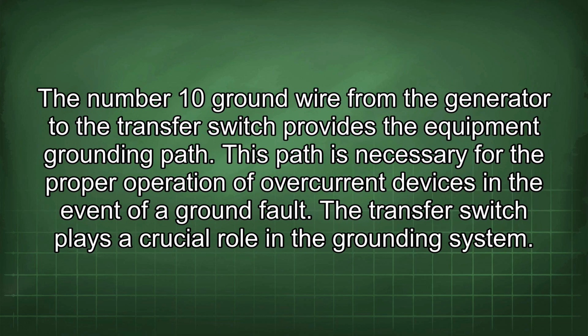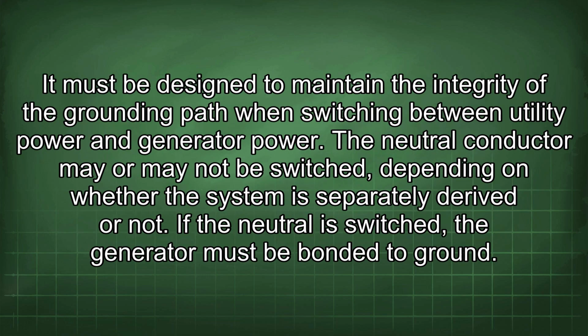The number 10 ground wire from the generator to the transfer switch provides the equipment grounding path. This path is necessary for the proper operation of overcurrent devices in the event of a ground fault. The transfer switch plays a crucial role in the grounding system. It must be designed to maintain the integrity of the grounding path when switching between utility power and generator power.